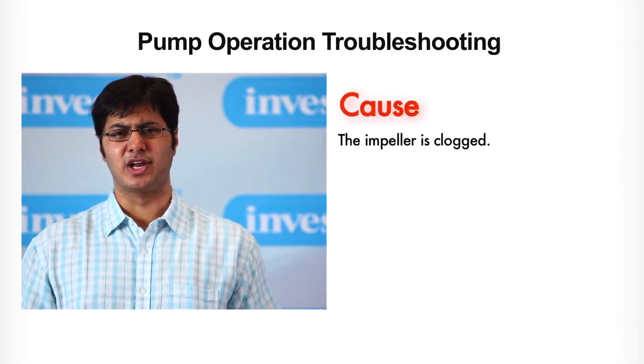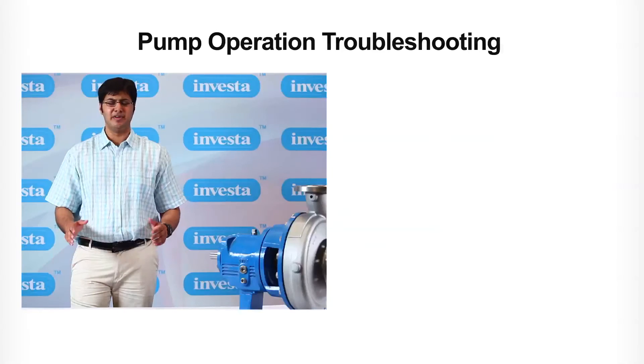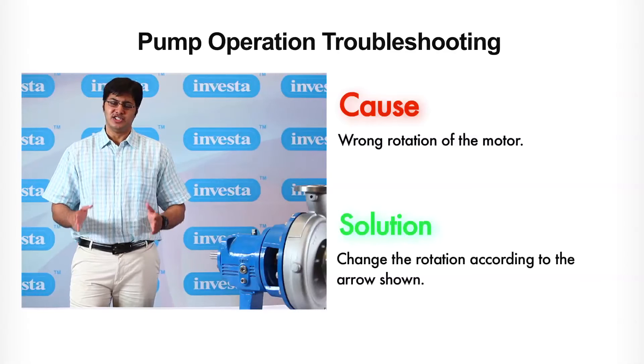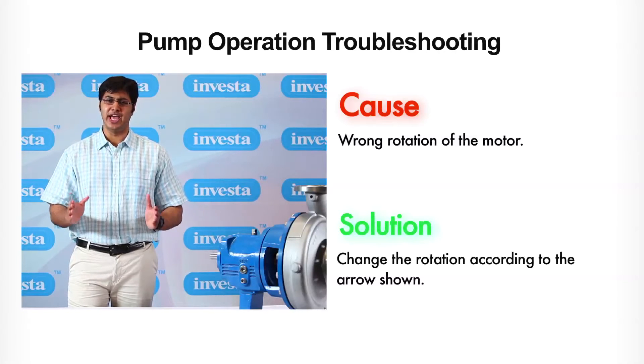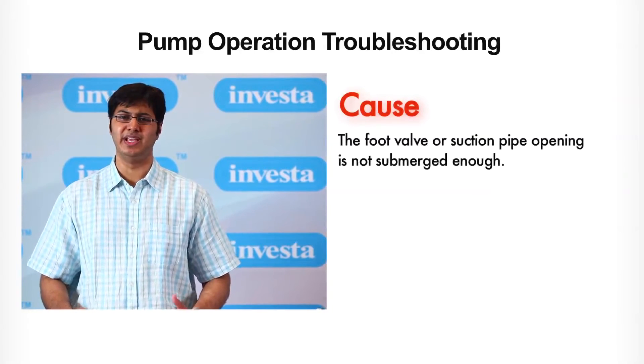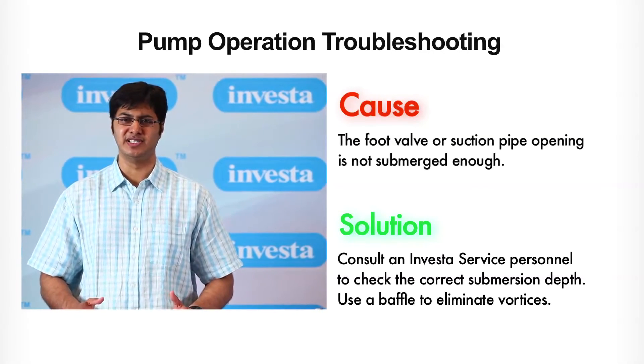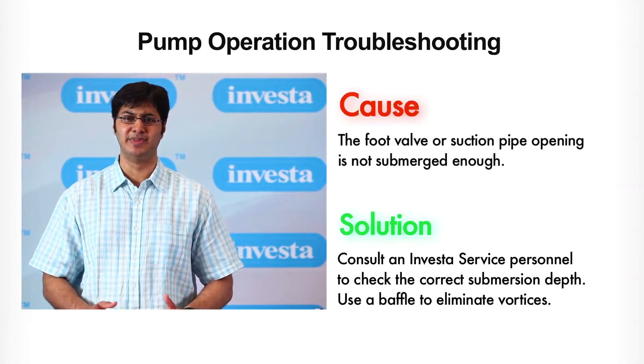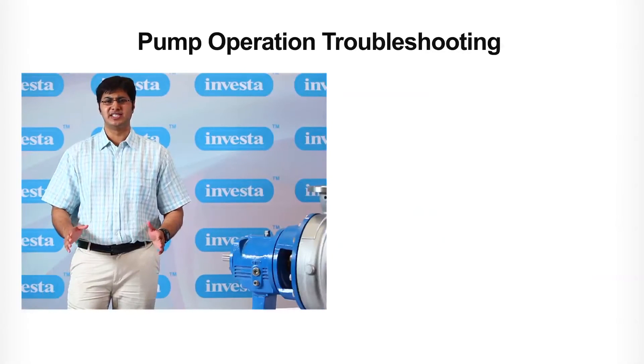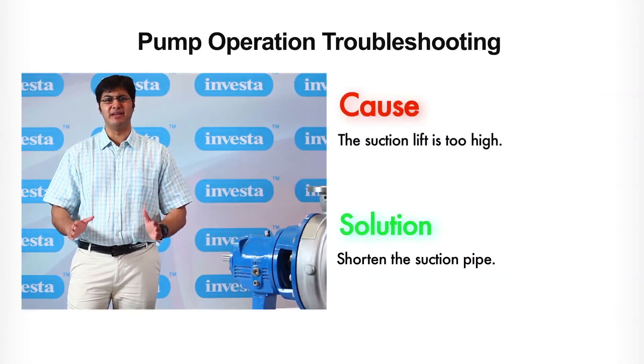Number three: the impeller is clogged — back flush the pump to clean the impeller. Number four: wrong rotation of the motor — change the rotation according to the arrow shown. Number five: the foot valve or suction pipe opening is not submerged enough — consult Investa service personnel to check the correct submerged depth. Use a baffle to eliminate vortices.